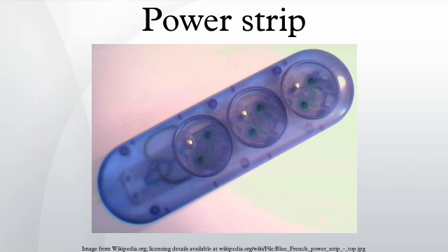Daisy chaining of power strips, whether surge protected or not, is specifically against most codes. As an example, the International Code Council's International Fire Code 2009 edition, section 605.4.2, states, "Relocatable power taps shall be directly connected to permanently installed receptacles."